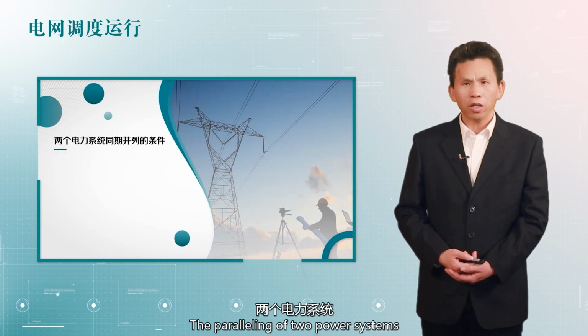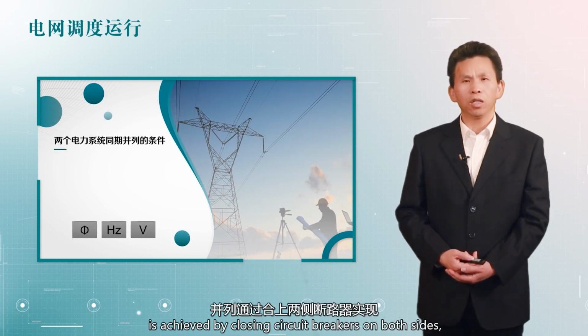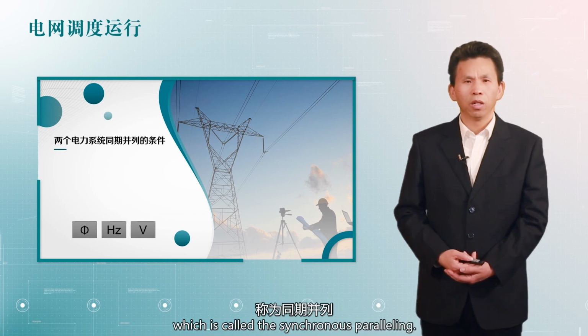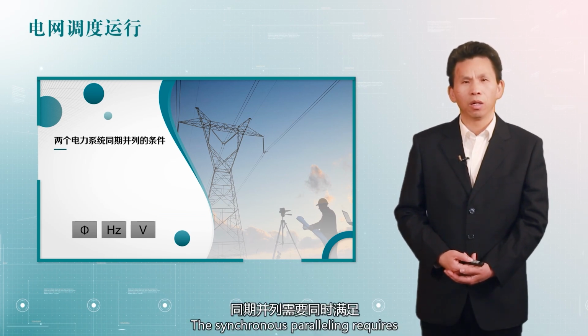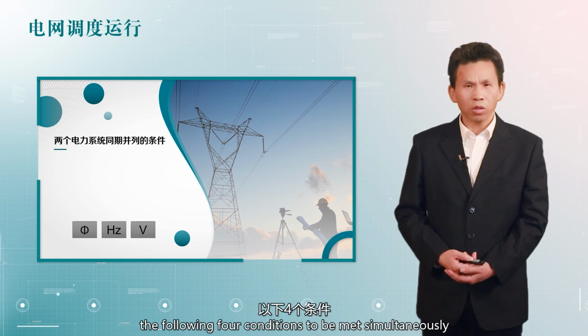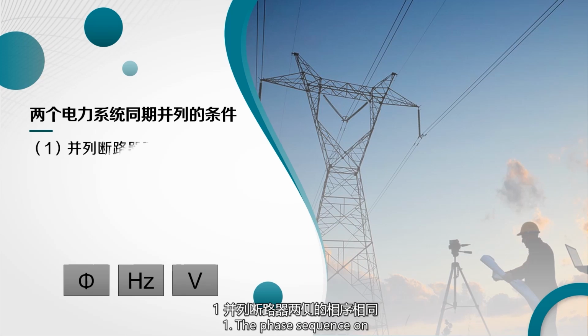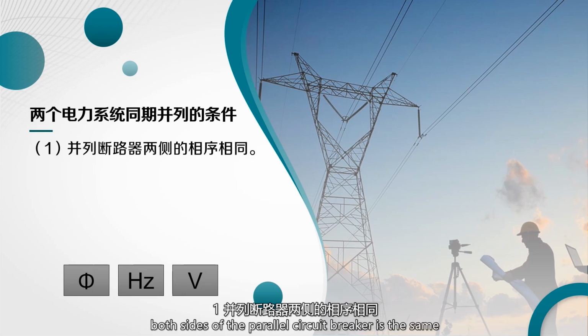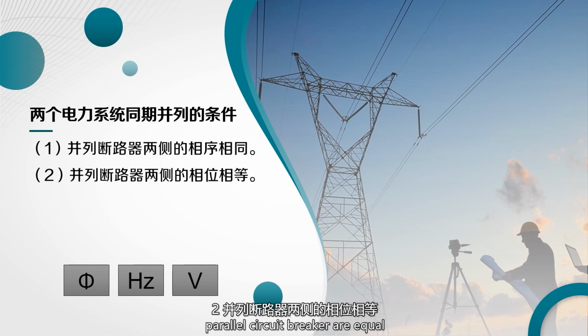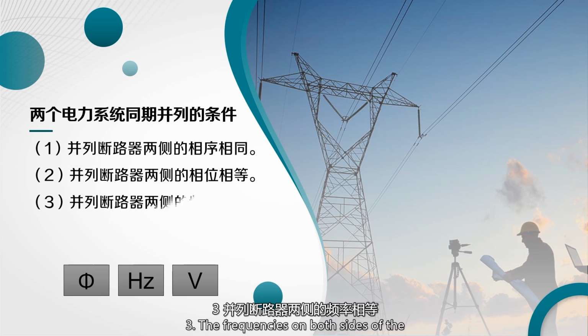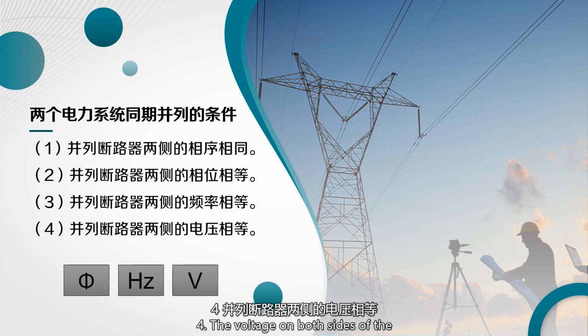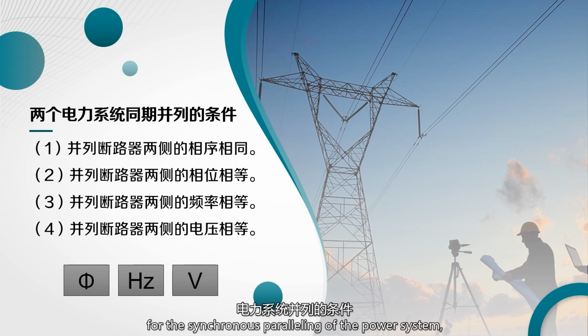The paralleling of two power systems is achieved by closing circuit breakers on both sides, which is called synchronous paralleling. Synchronous paralleling requires the following four conditions to be met simultaneously. 1. The phase sequence on both sides of the parallel circuit breaker is the same. 2. The phases on both sides of the parallel circuit breaker are equal. 3. The frequencies on both sides of the parallel circuit breaker are equal. 4. The voltage on both sides of the parallel circuit breaker is equal. You should remember the conditions for the synchronous paralleling of the power system.